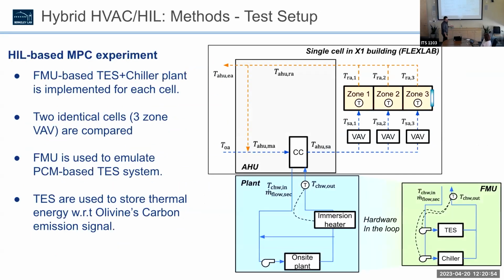So we conducted a test in FlexLab where we had a hardware-in-the-loop approach. We modeled a thermal energy storage integrated system in Modelica, compiled it into something called a functional mockup unit, and then created a hardware-in-the-loop interface where we're actually able to match the output of the model into the water loop at FlexLab, and then run the simulations that way, getting data from FlexLab based on what's going on at the plant level.